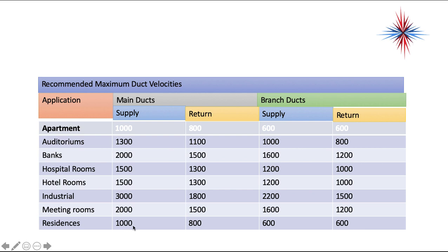Those values vary depending on the use of the building. Velocity has two main effects: if it's too high, it creates a lot of noise; if it's too low, we're not moving enough air and you could have condensation, dust, and dirt buildup in the ductwork. So the velocity needs to be appropriate according to the plans.